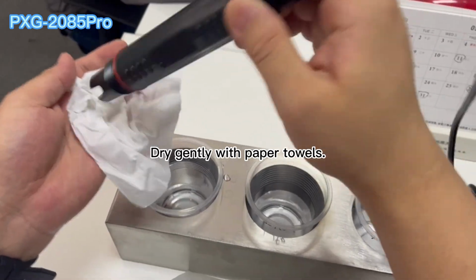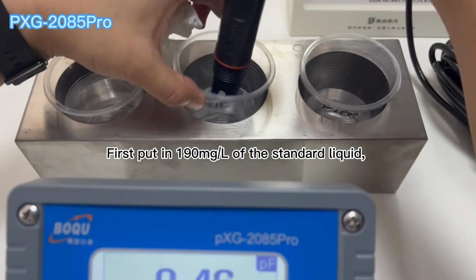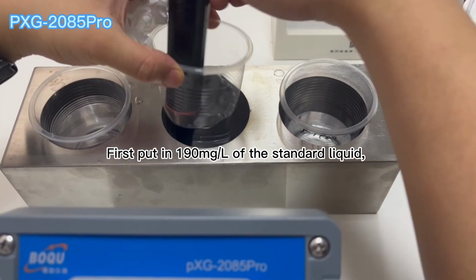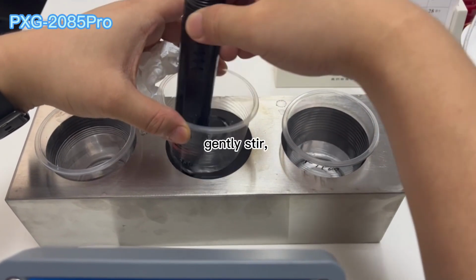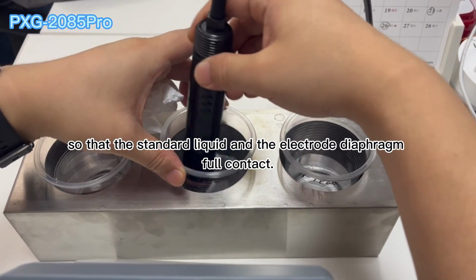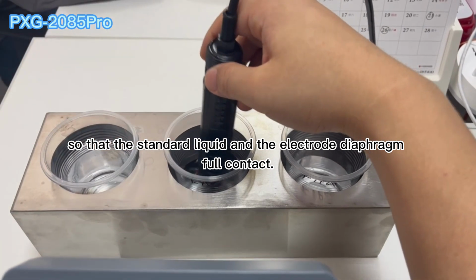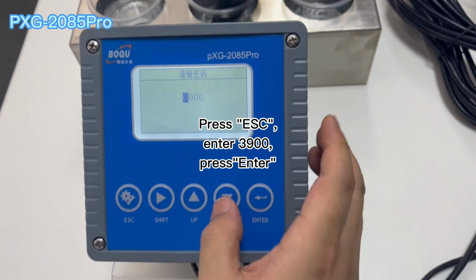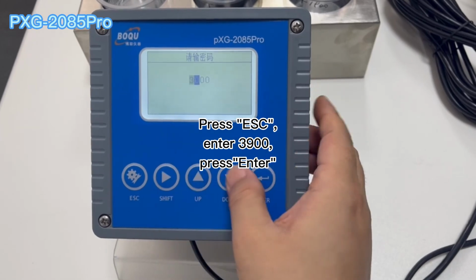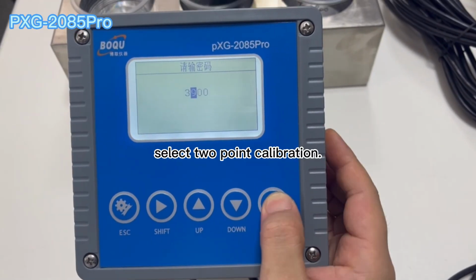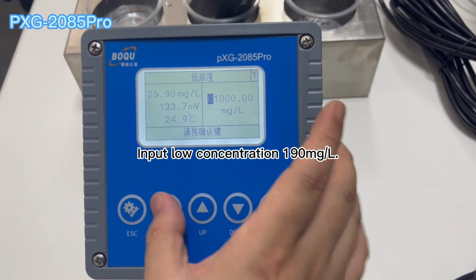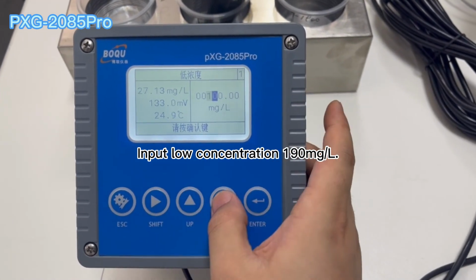Dry gently with paper towels. First put in 190 mg per liter of the standard liquid. Gently stir so that the standard liquid and the electrode diaphragm are in full contact. Press ESC. Enter 3900. Press Enter. Select 2-point calibration. Input low concentration 190.